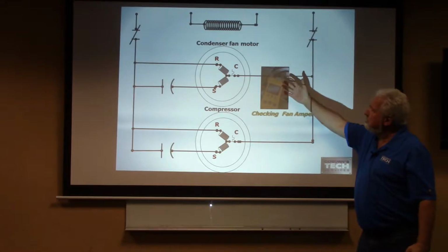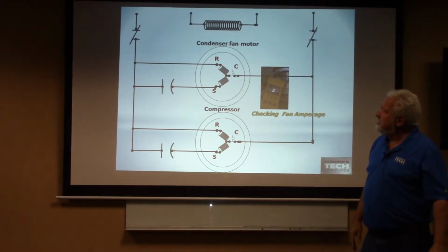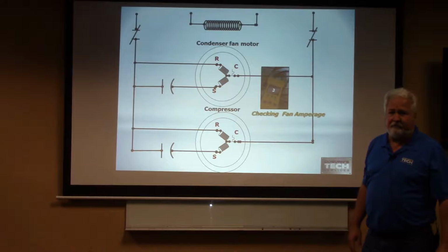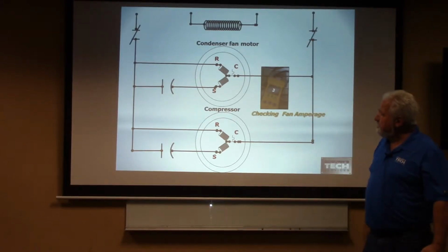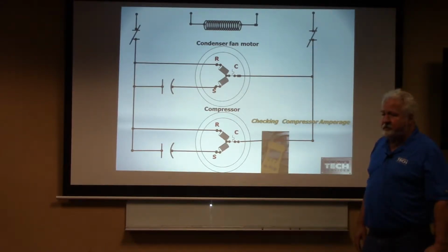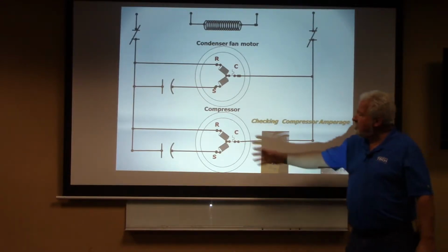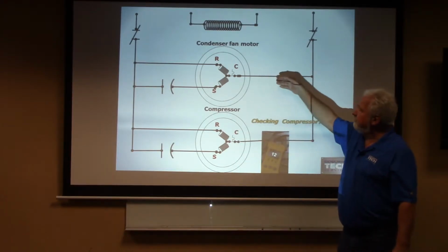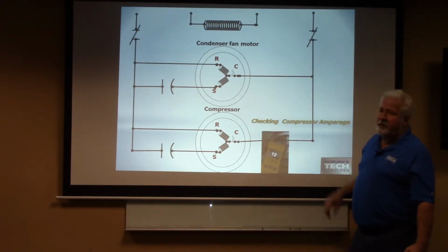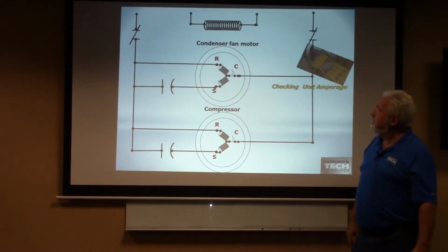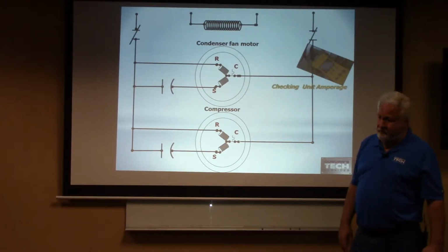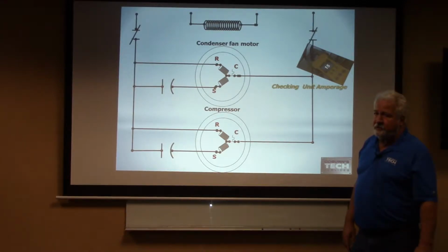In this particular case, we're going to get a condenser fan reading, and we might get 3 amps on that condenser fan motor. If we took our amp meter and brought it down to here, I may see what? 12 amps? Good. So my current flow through here is 12 amps. Current flow through here was 3 amps. If I went back to a common wire between the two of them, what should I expect to see here? 15 amps. Very good. So again, it's just the magnetism around the outside of the wire, which is going to be the flux that we're going to be able to pick up that amperage.